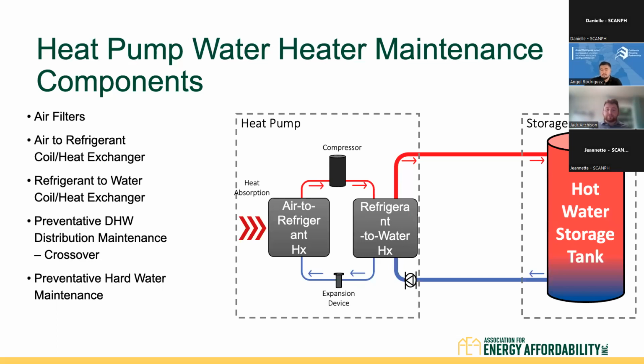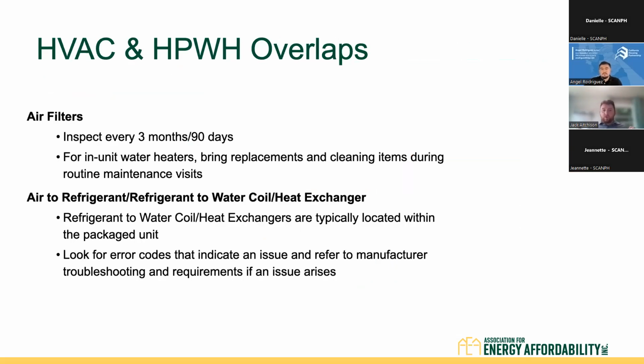Next slide, please. So just to go over a quick HVAC and heat pump water heater overlaps. You have an air filter. You should be inspecting those every 3 months / 90 days. For in-unit water heaters, bring replacements and cleaning items during routine maintenance visits. Ultimately, same thing as when you're replacing an air filter for an HVAC system. If you have access to that unit, you should be bringing filters with you. You should be bringing cleaning solutions with you so that you can replace that filter during a routine maintenance visit. And then air to refrigerant and refrigerant to water coil heat exchangers.